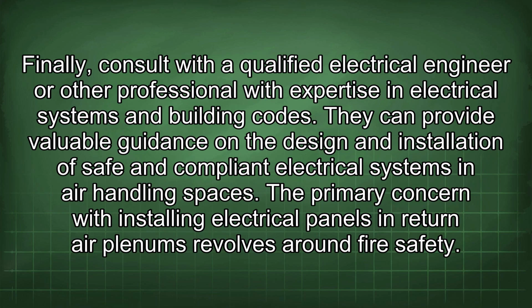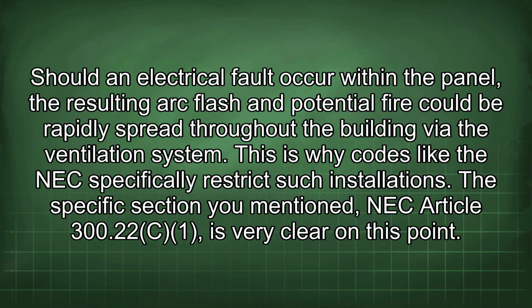Finally, consult with a qualified electrical engineer or other professional with expertise in electrical systems and building codes. They can provide valuable guidance on the design and installation of safe and compliant electrical systems in air handling spaces. The primary concern with installing electrical panels in return air plenums revolves around fire safety. Should an electrical fault occur within the panel, the resulting arc flash and potential fire could be rapidly spread throughout the building via the ventilation system.